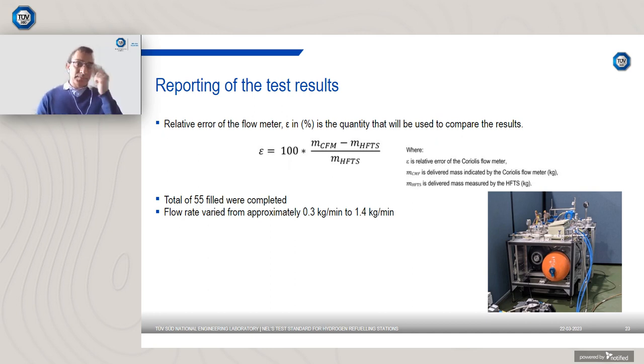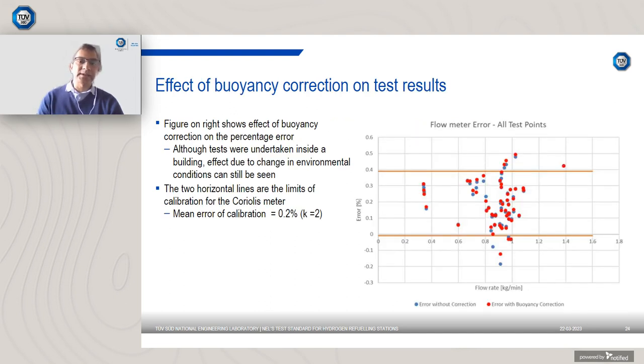The results that we are going to report next are given according to the relative error of the flow meter, and it is defined as per the expression that's shown here. So you've got the Coriolis flow meter reading as well as the mass measurement from the test rig's gravimetric system. We carried out a total of 55 tests, and during each of those tests, we essentially ensured that the nitrogen gas flow rate was between 0.3 kilograms per minute and 1.4 kilograms per minute. The reason for this is because this was a range at which we had calibrated the Coriolis flow meter at NEL.